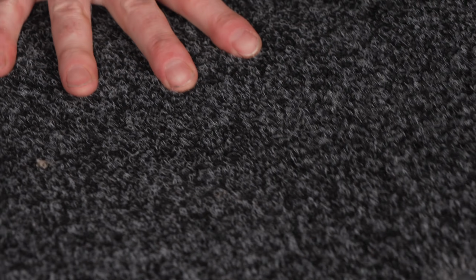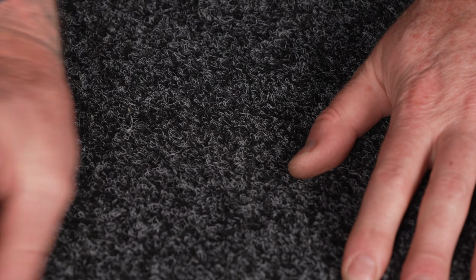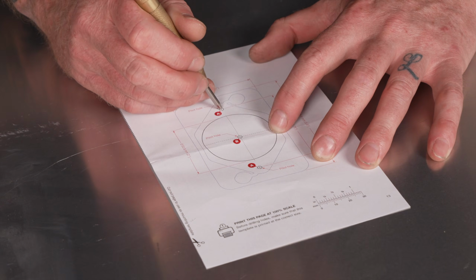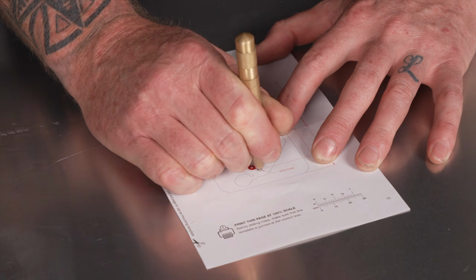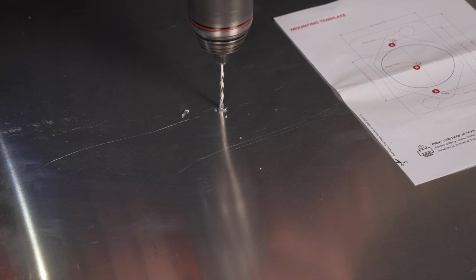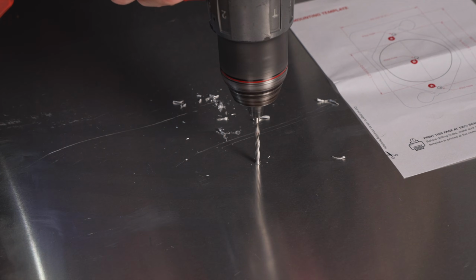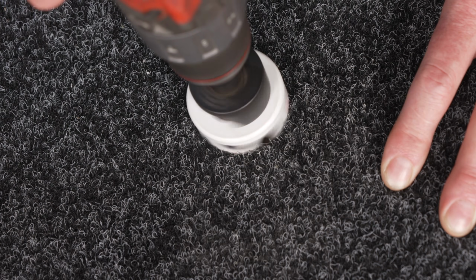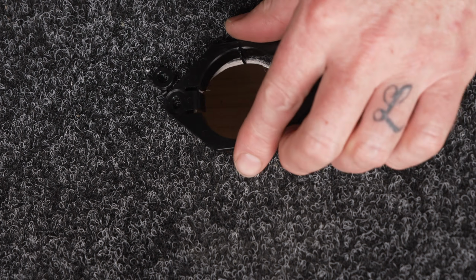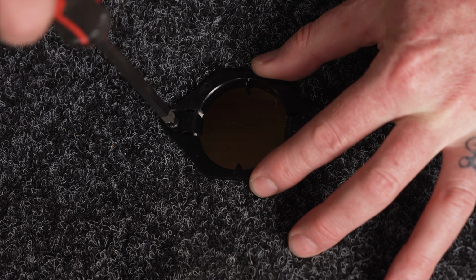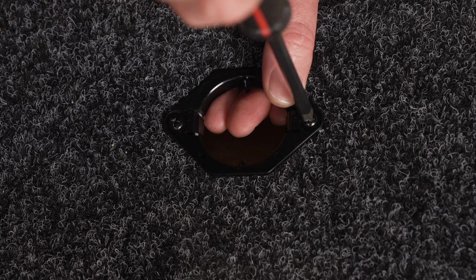Begin by choosing a mounting location for your RedVision Essentials display. Ensure it's in an interior, flat, visible location that utilises both mounting holes. First, use the mounting template to mark out the points labelled A and B. Remove the template and drill pilot holes using a 3mm or 1/8 inch drill bit, then drill point B using a 51mm or 2 inch drill bit. Deburr the holes and fasten the mounting bracket into place using the supplied screws.